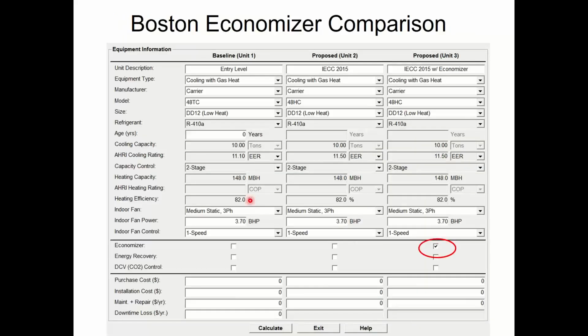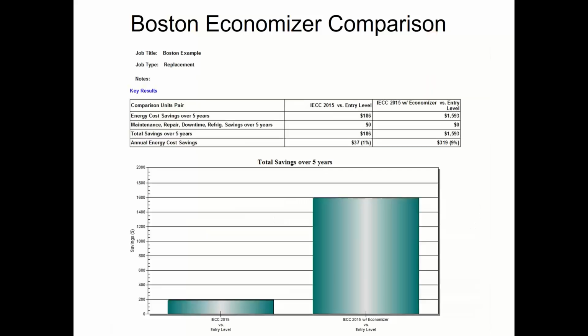If I go back to that same software tool I was using before, I have a basic unit. I have this 2015 code compliant unit. 2018, as far as the equipment efficiency table goes, is the exact same code compliancy. So I didn't update my slide here, but this would be the same for 2018. I would still need the same efficiency here, 11.5 EER and whatever the IEER was on the backside. So a basic, simple, low-end unit that's not code compliant, versus a current, code compliant unit with an economizer.